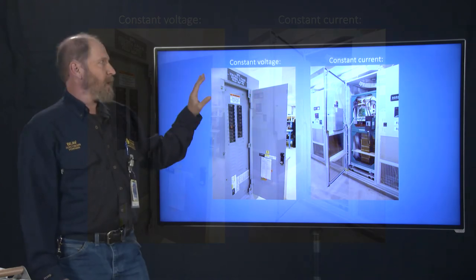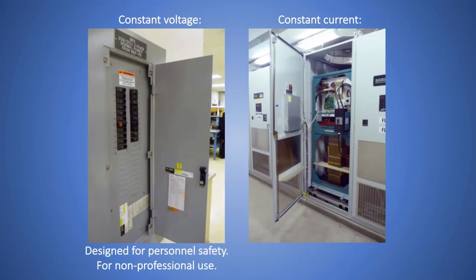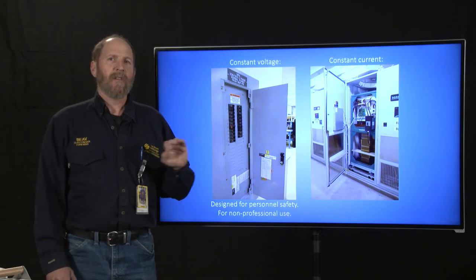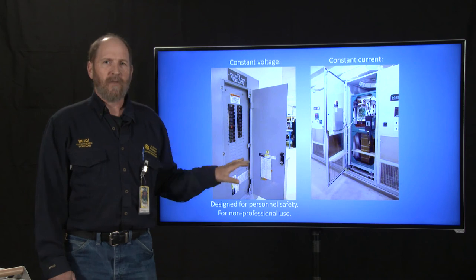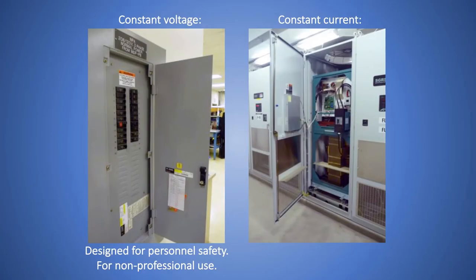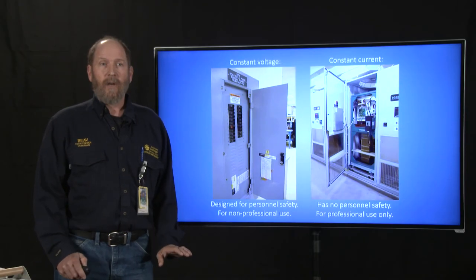The main difference between a constant voltage and a constant current system is that constant voltage is designed for personnel safety. Personnel safety is integrated into every portion of this system. It's designed so that I can use it, you can use it, my kids can use it, anyone in the public can use it safely. It's also designed to protect property from fire and other hazards. Now, a constant current system, on the other hand, has absolutely no personnel safety integrated into it.